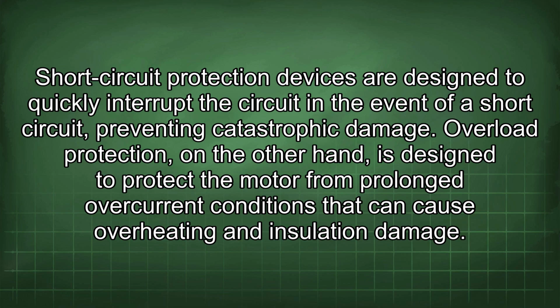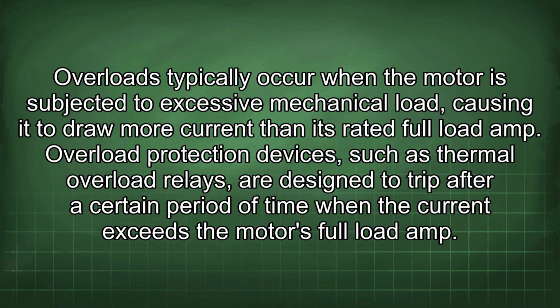damage. Overload protection, on the other hand, is designed to protect the motor from prolonged overcurrent conditions that can cause overheating and insulation damage. Overloads typically occur when the motor is subjected to excessive mechanical load, causing it to draw more current than its rated full load amp. Overload protection devices, such as thermal overload relays, are designed to trip after a certain period of time when the current exceeds the motor's full load amp.